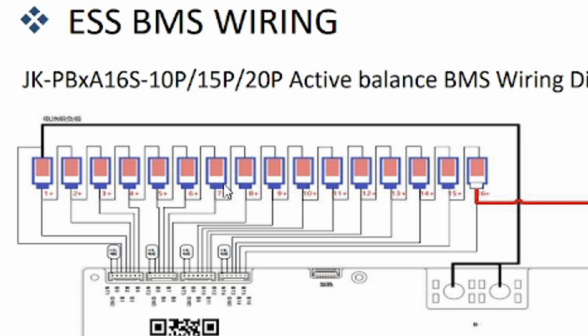So in a balancing case, if it determined cell 2 had lower voltage, it would find the higher voltage cell, extract some electricity from it, store it, and then put it back into cell 2, causing the high cell to go down a tiny bit and the low cell to go up a little bit. That's what active balancing means: it's actively taking power from the highest cell and transferring it to the lowest cell, one cell at a time.